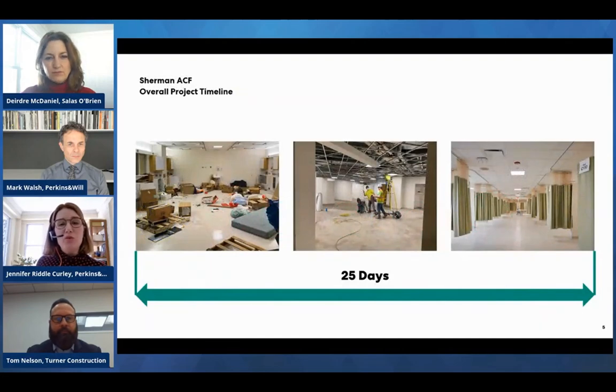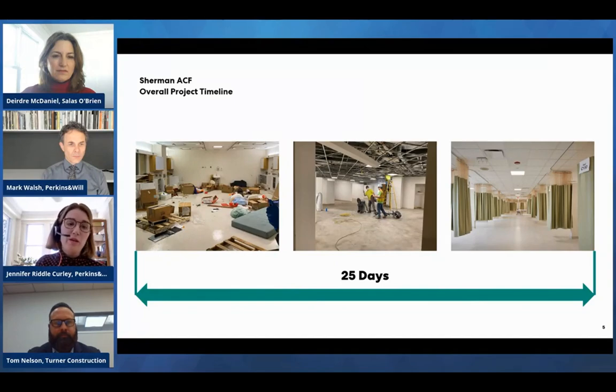The building we came into on March 30th of last year was in pretty rough shape. It had been unused for a number of years. There was a serious amount of disarray. We found areas and parts of the project that had suffered water damage. Major medical equipment had been left in place. MEP systems were left in place, and there was supply and debris scattered about. The MEP systems had not been maintained for years. There were no medical gases piped into the site. And from a medical planning perspective, there was limited existing spaces that were readily suitable for patient bays.